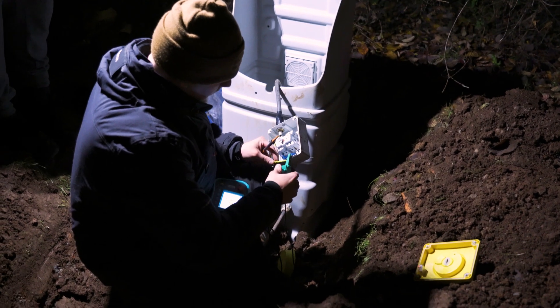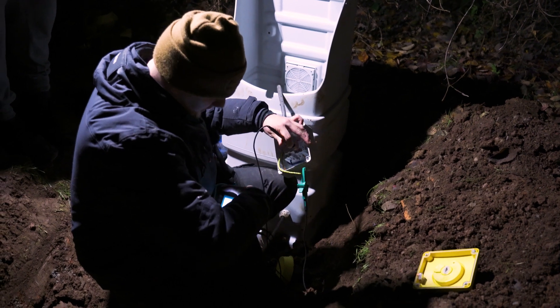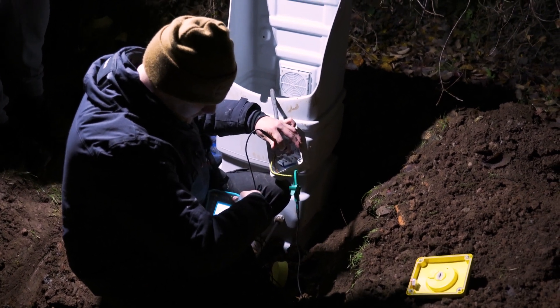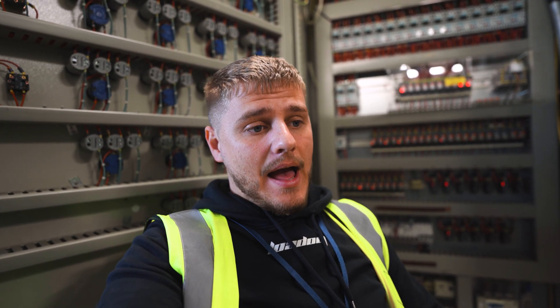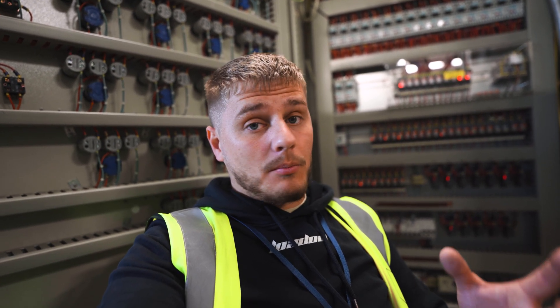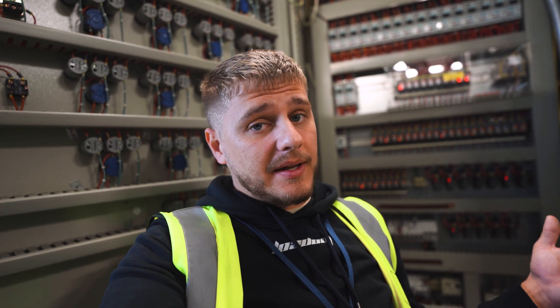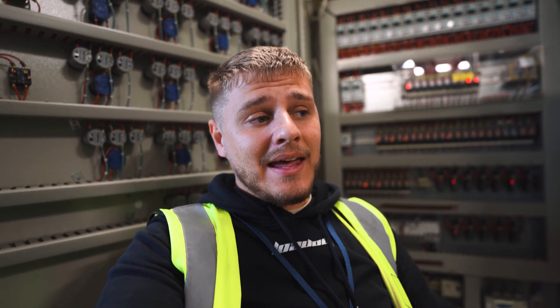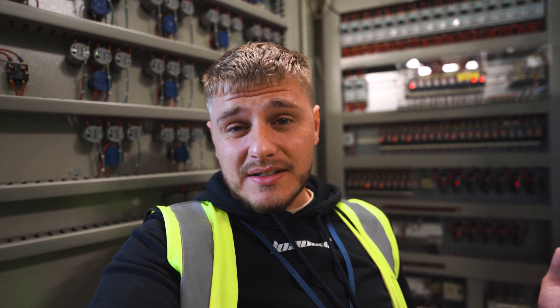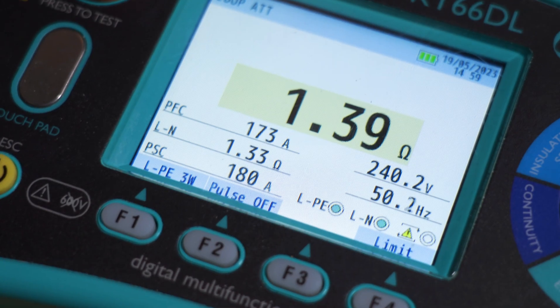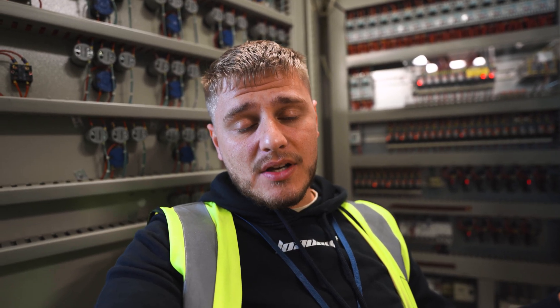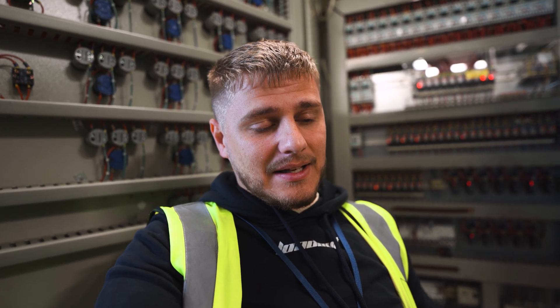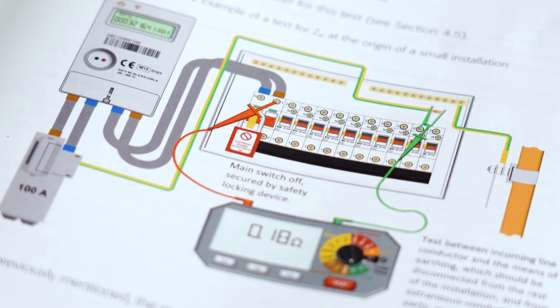Earth fault loop impedance testing is probably the easiest test to actually carry out or calculate, but it's also one of the most important. Before we get into that, you might want to know what impedance is and what loop means. Impedance is basically the same as resistance just under live conditions — impedance is voltage divided by current — both measured in ohms and both essentially the same thing.